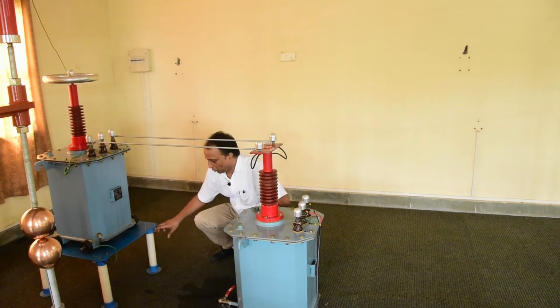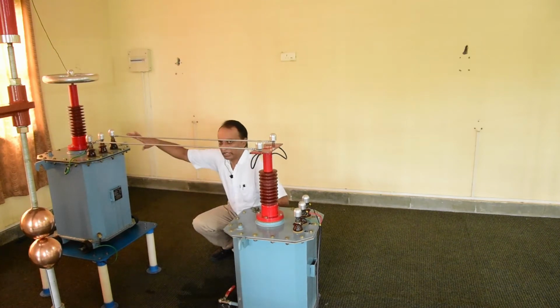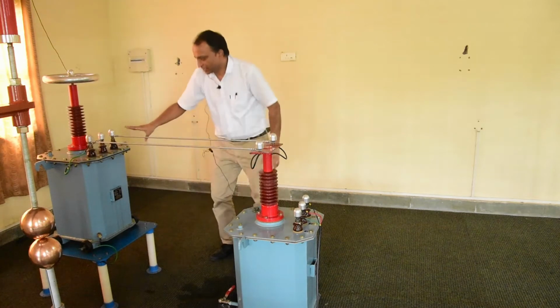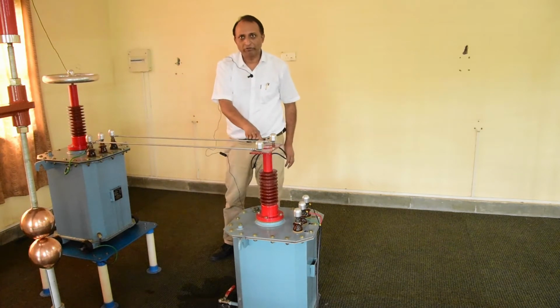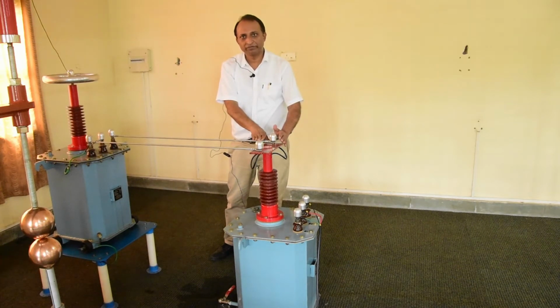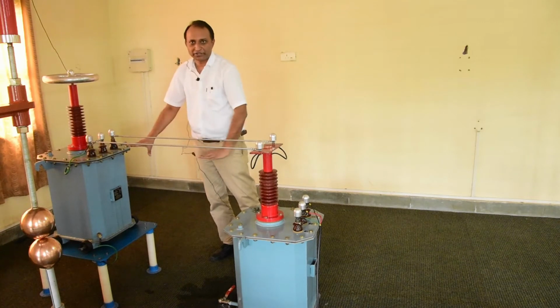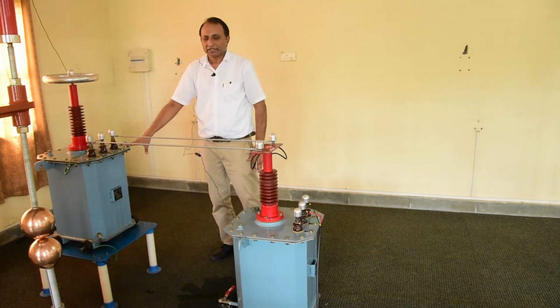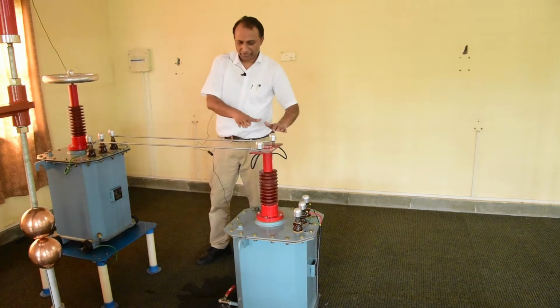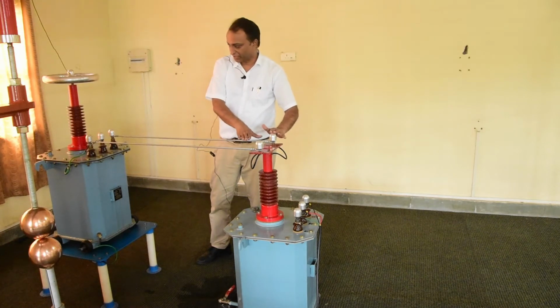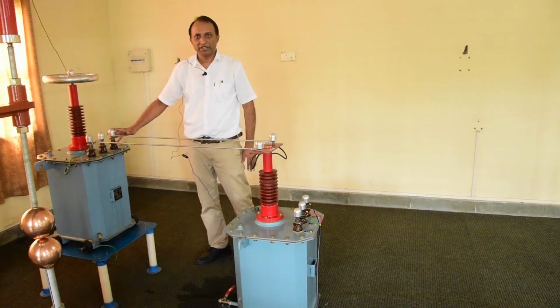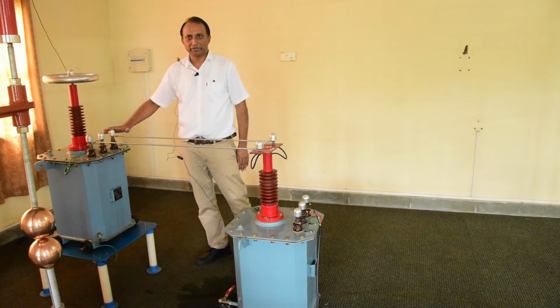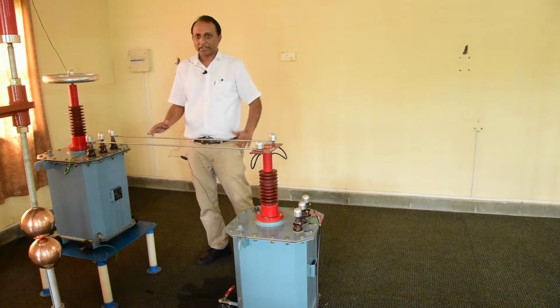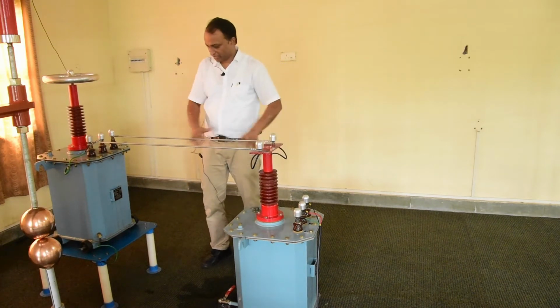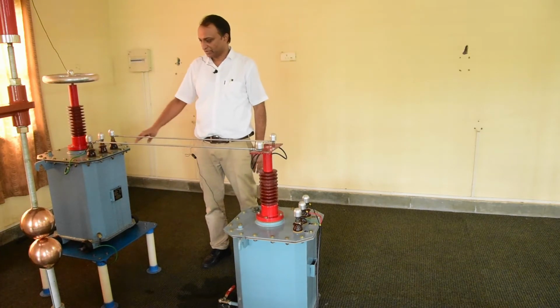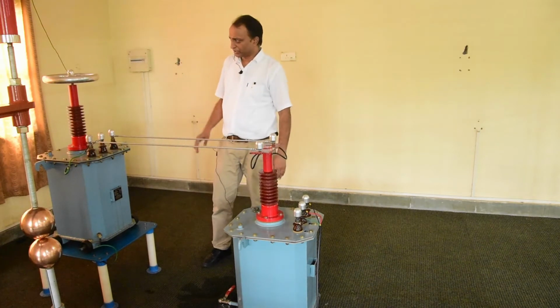platform. This platform provides an isolation of 50 kV because the tank of the second transformer is to be maintained at the output voltage of the first stage. Output voltage of first stage is 50 kV, and reference potential of the second stage, that is the tank potential, is 50 kV. So the first stage providing 50 kV, the secondary of the first stage will come in series with the secondary of the second stage transformer. So 50 kV plus another 50 kV. Together the output voltage that can be generated using this cascade connected transformer is 100 kV maximum. This is a single phase.